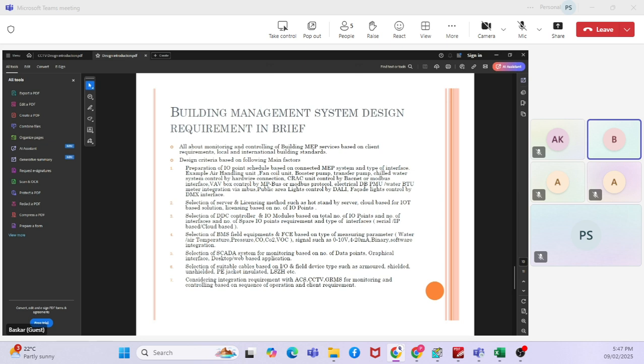Selection of server and licensing, again, is based on the number of IO points. IO points can be software IO points or hardware IO points. Hardware points are analog inputs, analog outputs, digital inputs and digital outputs. With software, we have software monitoring points and software control points, and in that itself you will have analog points and digital points. So you need to choose the servers and the licensing based on the IO points and the type of IO points. Cumulatively, how many analog inputs, how many analog outputs, how many Modbus points there are, all has to be defined in the IO points, and based on that, the licensing on the server has to be chosen.